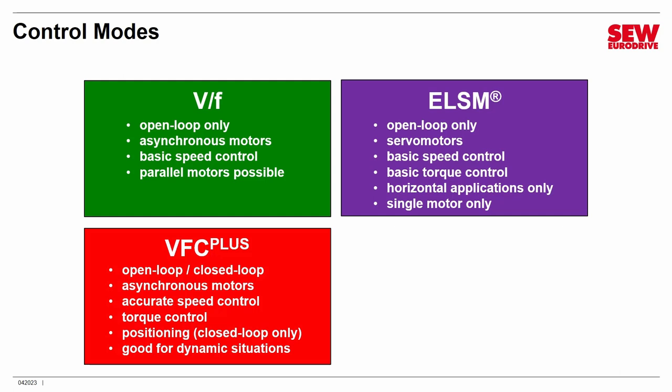Other brands of VFDs have things that are sort of like this that they generally call vector control modes — a similar idea, but VFC+ is our particular form of it, and we've really perfected it. It's also good for situations with very dynamic operations where you're changing speed and direction quickly and precisely. If you've got an asynchronous motor, use VFC+ rather than VF mode — you will get better results.